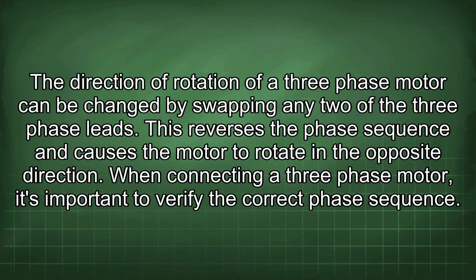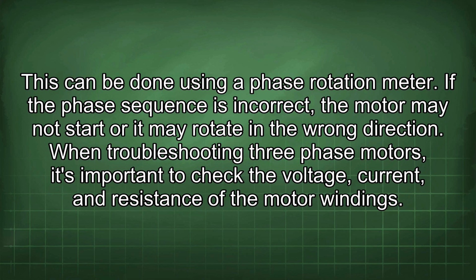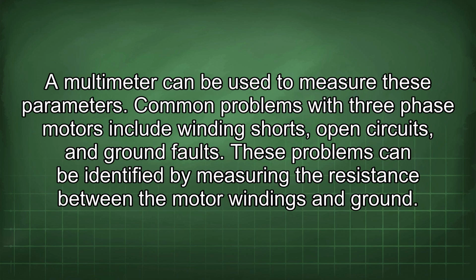When connecting a three-phase motor, it's important to verify the correct phase sequence. This can be done using a phase rotation meter. If the phase sequence is incorrect, the motor may not start or it may rotate in the wrong direction. When troubleshooting three-phase motors, it's important to check the voltage, current, and resistance of the motor windings. A multimeter can be used to measure these parameters.